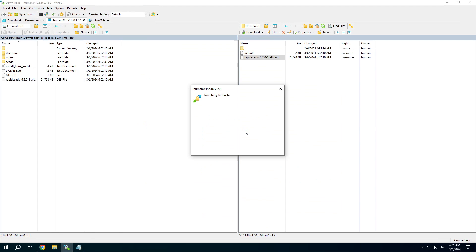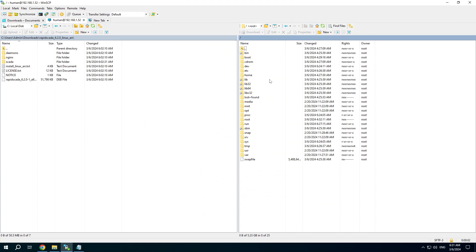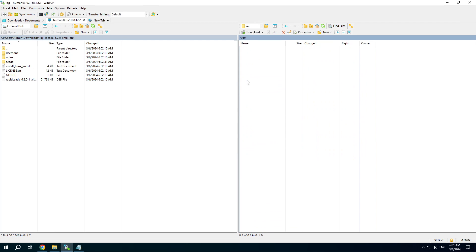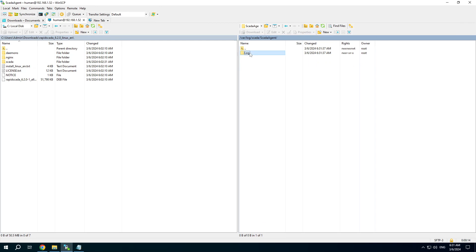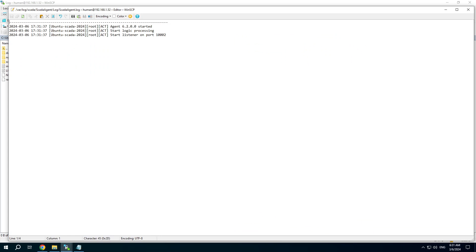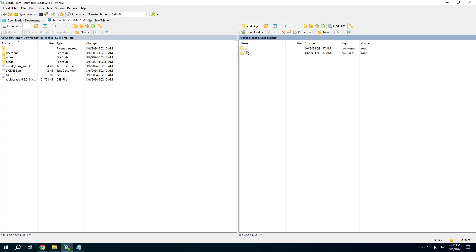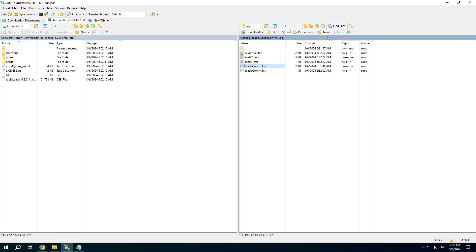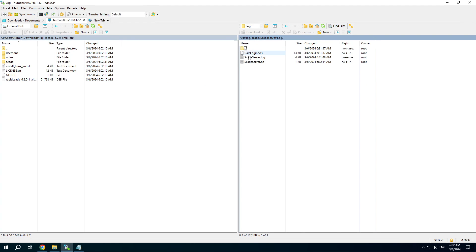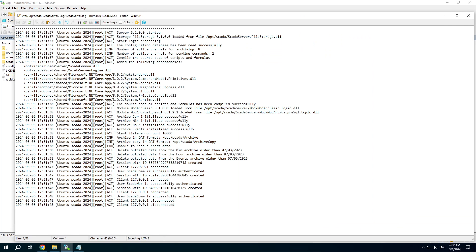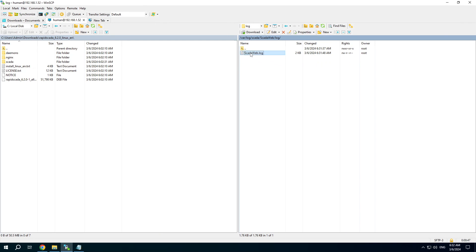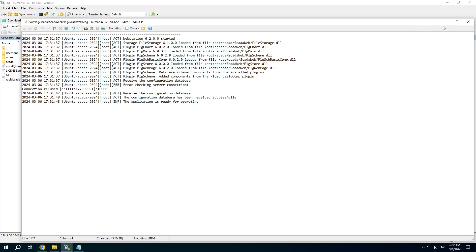Reconnect again. The server is already restarted. And I want to check RapidSCADA log files. Press F4 to open the file. Agent was started. Communicator is started. Server works well. And the webstation application is also good.